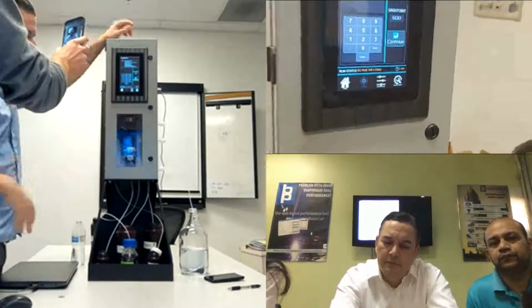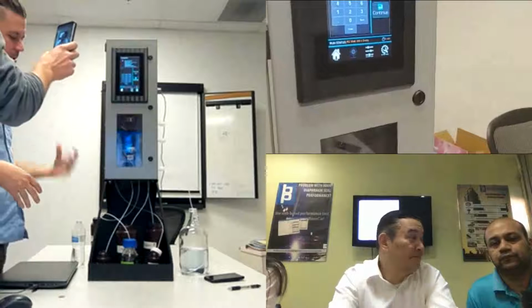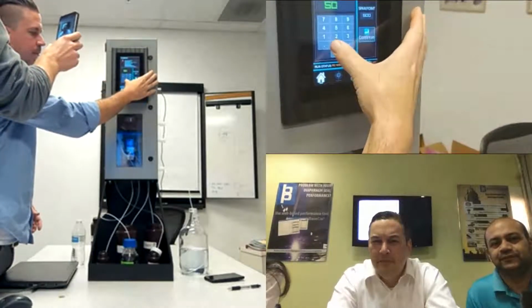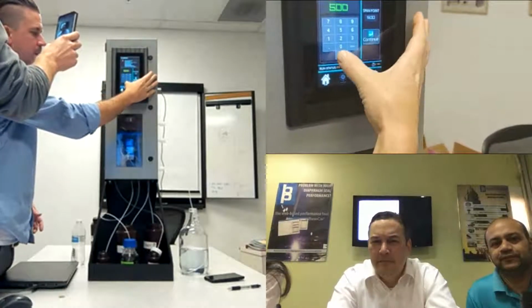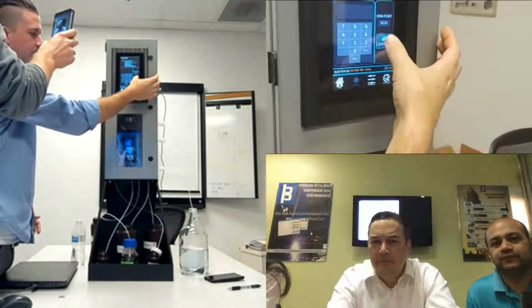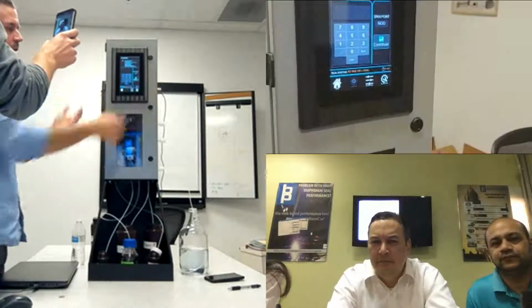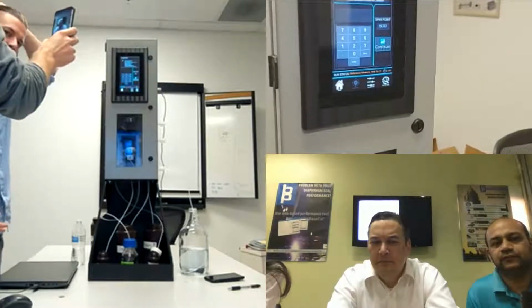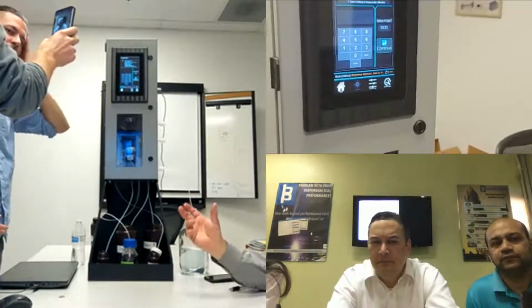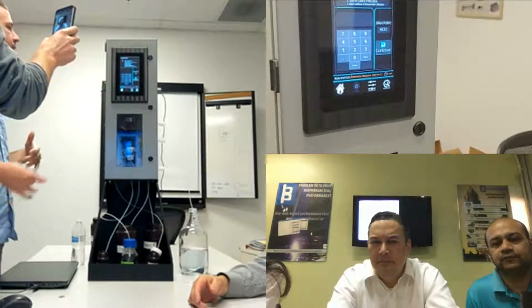It's extremely simple. The calibration process really only involves having a calibration standard connected to the unit, simply typing in the value you want to calibrate to, 500 ppb, and hitting go. So you just hit continue. It will automatically step through all the processes needed to calibrate zero and span points for the instrument. Super simple, couldn't be easier to do.